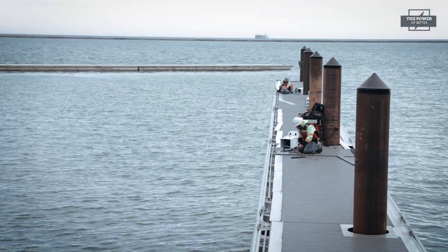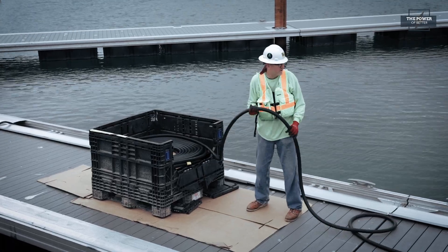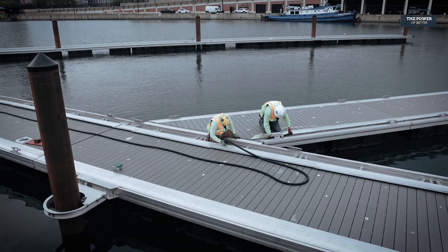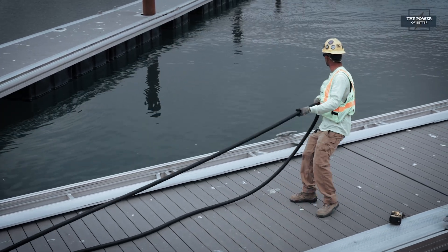When the materials arrived on site, the 40,000 feet of marine cabling had to be delicately installed underwater, many times on docks that were constantly shifting in the water. We stretched it out on the dock itself, then pulled it up through underwater conduit that stubbed down into the water approximately five feet on each end, and then slowly lowered the cable down into the water. It was a bit of a learning curve — it probably took a crew of five guys to do each cable, and we had a total of six cables to complete.